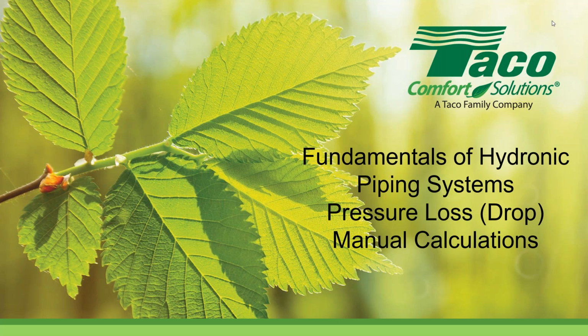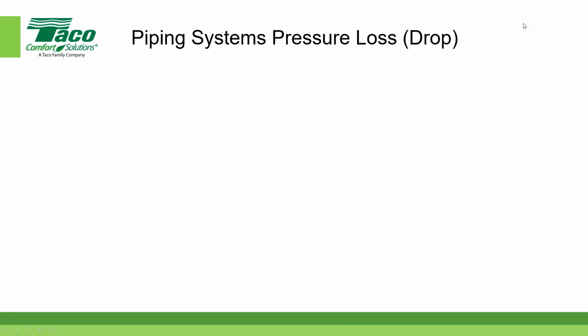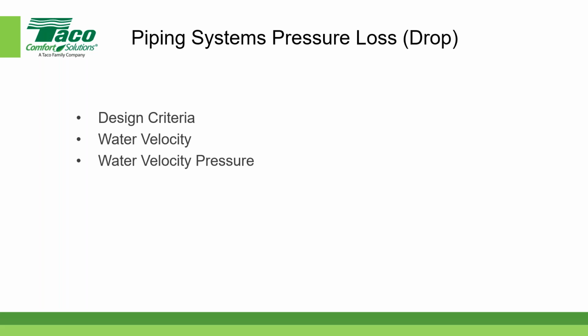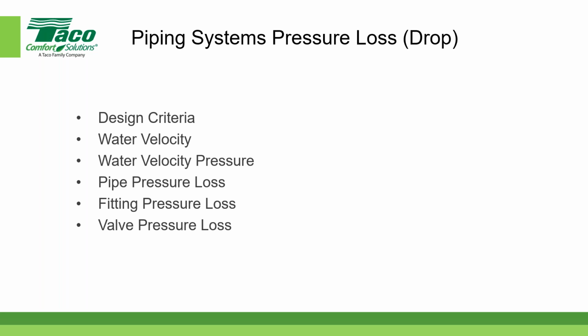Okay, so let's talk a little bit about what we're going to do here. Let's see, does this thing work? So let's talk a little bit about design criteria. What does that really mean? And we'll touch on water velocity and then water velocity pressure. Then we'll get into the pipe pressure loss calculations. And again, this is a manual calculation, and we're going to compare that against a computer calculation. We'll talk about fitting losses, valve losses, and we'll also define what the valve CV is all about.